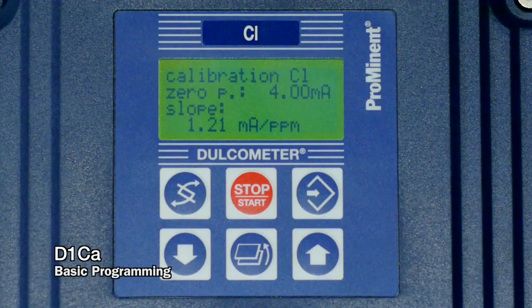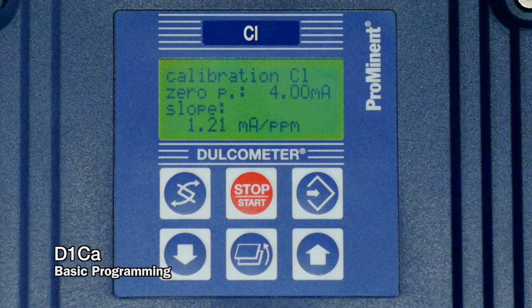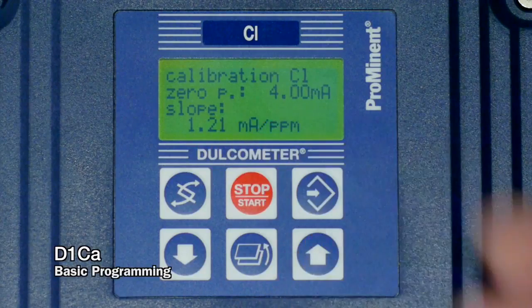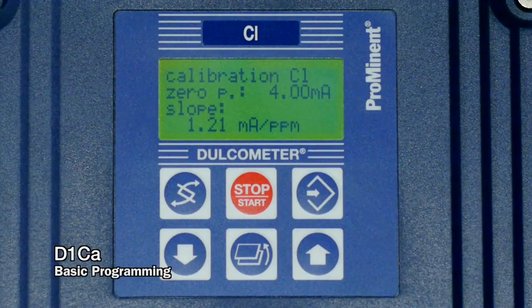So that starting slope value, here we're at 1.2. It's actually 1.20 for a 10 part per million sensor is the starting slope value. It will accept the calibration until we get to 25% of that calculated slope, or in this case, 0.30 milliamps per part per million. It will accept that calibration. If we go any further and the resulting slope would be 0.29 or below, and this is on a 10 parts per million sensor, the calibration will not be accepted. It will say slope is too low and calibration is denied.